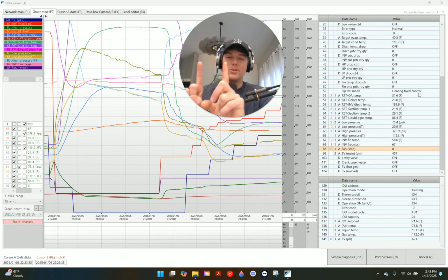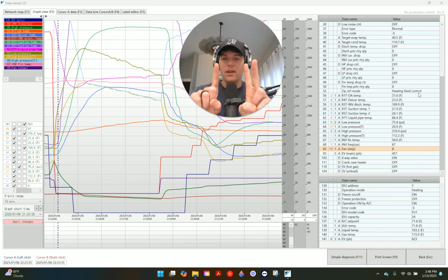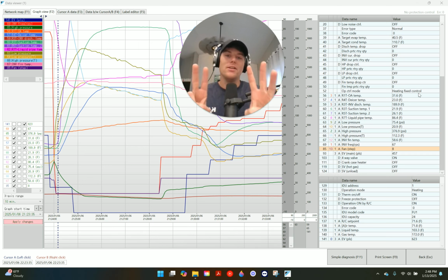Okay. You know what? To really get a clear picture of these 2 things and why there's a problem, let me add this thing and then this thing. Oh, and there's all this other thing over here. Okay. Now let me look at these together in that spot that I found a problem. The problem is very clear. This system is overcharged.